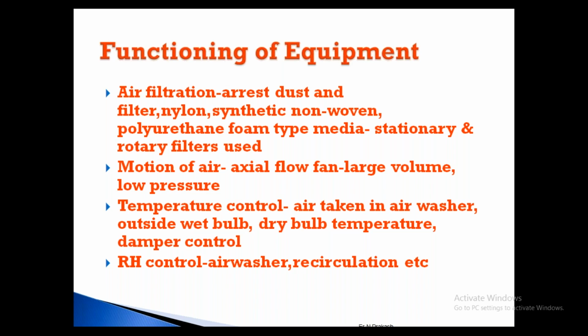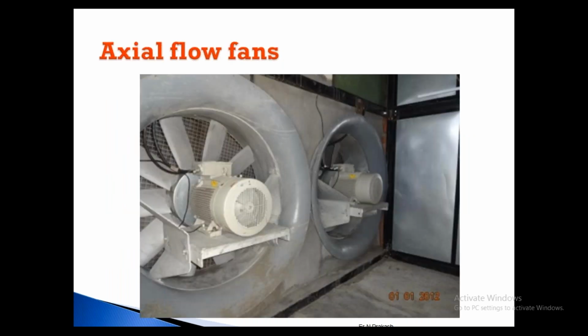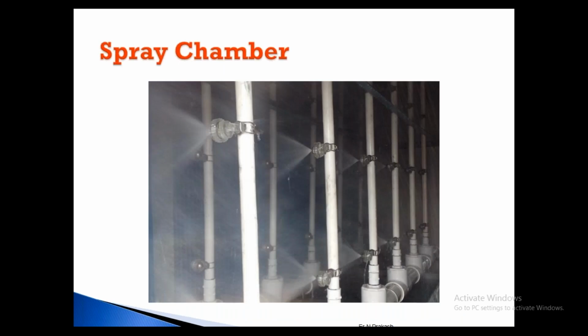So these are the equipments. We have the axial flow fans, and there are different types of fans. I'll explain next after a few slides. And we have an air washer chamber, a spray chamber, where the nozzles will be there. They will be evenly distributed, with this much nozzles per square foot, based on some design calculation. And there is no gap, so air doesn't escape past the water. It should be sprayed and spread in such a way that you get a good, efficient air washer.